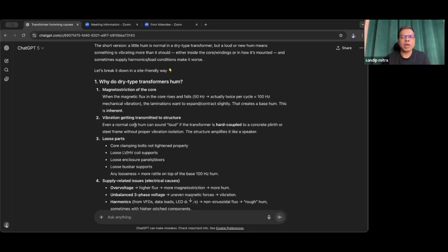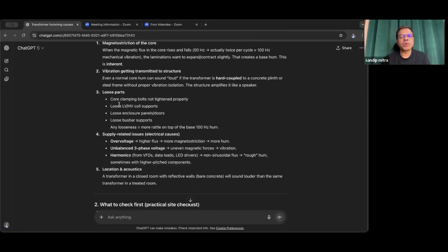This is inherent. Now, vibration getting transmitted to structure: even a normal core hum can sound loud if the transformer is hard coupled to a concrete plinth or steel frame without proper vibration isolation. The structure amplifies it like a speaker. Then loose parts: core clamping bolts not tightened properly, loose LV or HV coil supports, loose enclosure panels, loose busbar supports. Any looseness equals more rattle on top of the 100 hertz hum. Supply related issues, electrical causes: overvoltage means higher flux, more magnetostriction, more hum; unbalanced three-phase voltage gives uneven magnetic force and vibration; harmonics from VFDs, data loads, LED drivers, sometimes with higher pitched components.